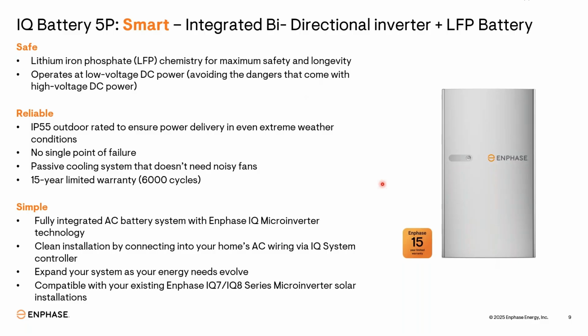You can expand your system very easily for future purposes. These AC coupled batteries have this advantage. The expansion is very easy. Today you have some requirements for batteries, so you install a single battery, which is 3.84 kW and stores 5 kWh of energy, 5 units of energy. In future, if the backup demand or the load demand increases for homeowners, you can simply put a battery in parallel to the existing one, connect your line, neutral and communication cable, and your installation is done.